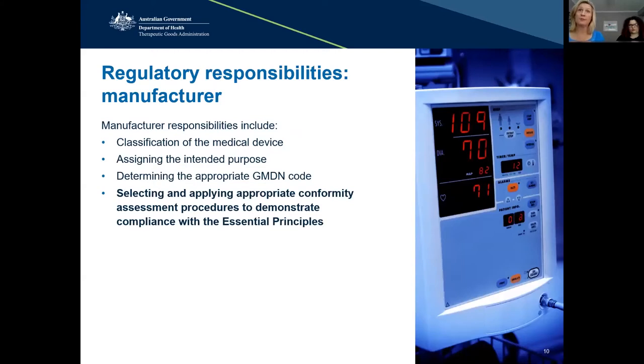The manufacturer is also responsible for assigning the risk classification and the intended purpose. Remember, it's the intended purpose of the device that determines the classification. The manufacturer assigns the GMDN term, then selects and applies the appropriate conformity assessment procedures to demonstrate compliance with the essential principles, which we'll talk about in more detail shortly.